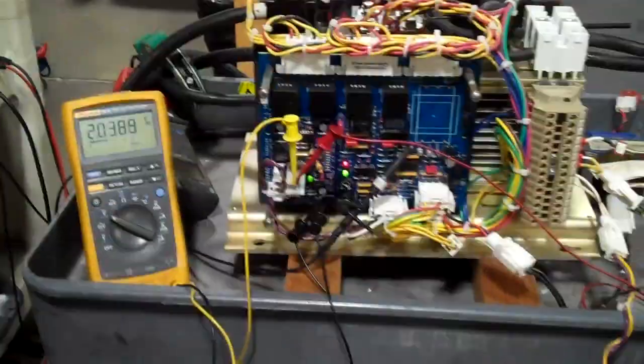That is the level that gets compared against R1 in the field loss. Right now the field loss is set at a maximum of 2 volts, and I'm going to ask Tony to adjust it to half a volt and then bring it back.